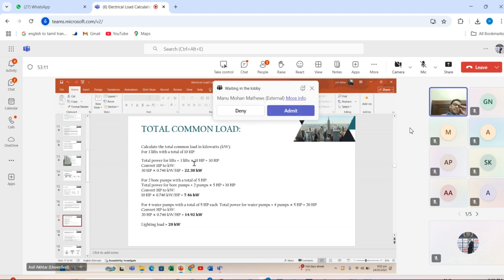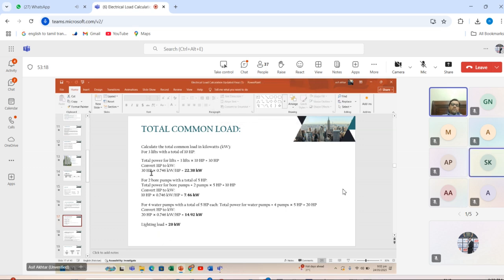Is this calculation clear? If anyone has a question, please ask me, otherwise I will go on. So for 2 bore pumps with a total of 5 HP, the total power for bore pumps is 2 pumps multiplied by a rating of 5 HP, which is equal to 10 HP. Now convert HP into kilowatt. The same formula will be used as above. So 10 HP multiplied by 0.746 kilowatt is equal to 7.46 kilowatt.